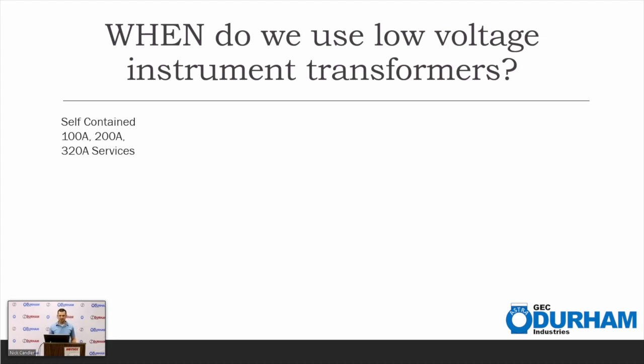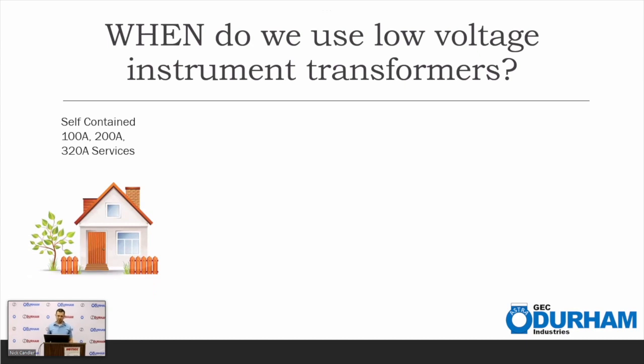Self-contained meter sockets can handle up to about 320 amps. Those are going to be the bulk of your residential homes. But anytime you get above 400 amps, that is when you're going to need to put in some instrument rated services. So old A-base and K-base enclosures tried to account for that, but we're seeing more and more that industry move away from those type of metering devices. So yeah, correct. 400 amps or greater, commercial, some industry, and some larger homes.